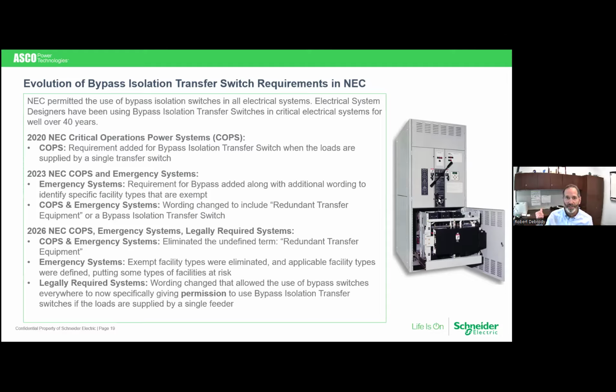The same way they addressed it with the generator, they said, look, I don't want that transfer switch to fail, and you have no way to get power around it to your loads that are so critical. So let's make sure that you put in a bypass isolation transfer switch to make sure that you can get around that transfer switch if it fails. So in 2023, they said, great idea for COPS, we ought to put it in emergency systems. So they did that same thing. They put it in for emergency systems.